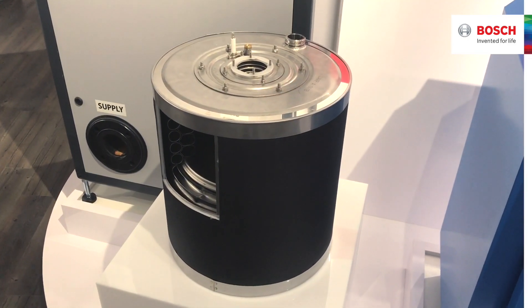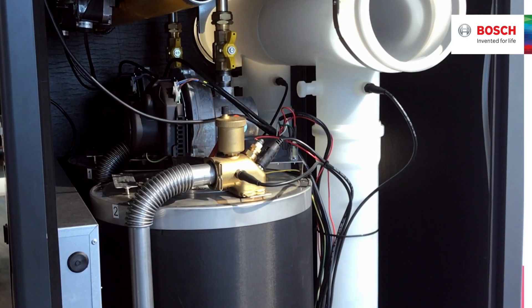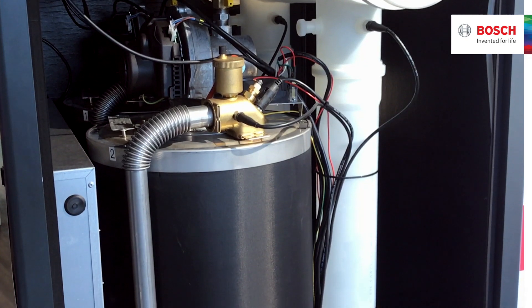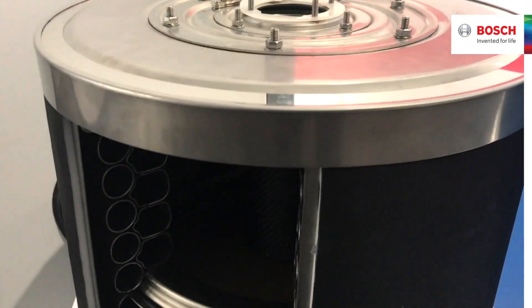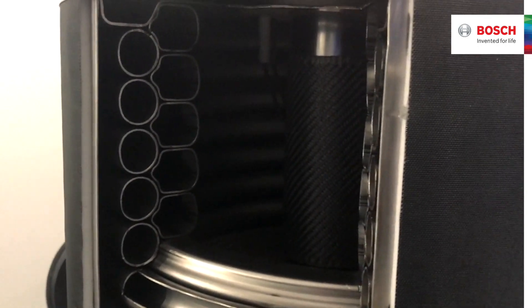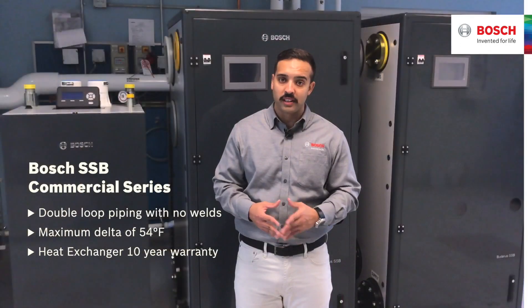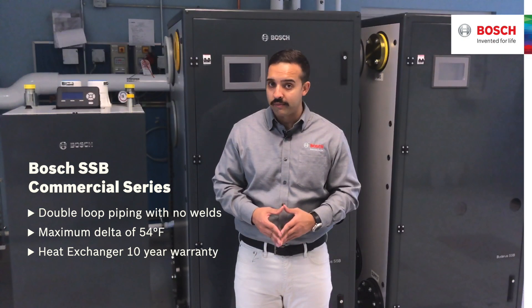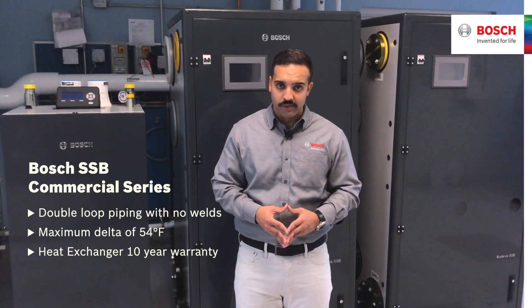The heat exchanger in all SSB boilers has a certified efficiency of 96% and a 5 to 1 turn down ratio. It is a water tube design made of 316L stainless steel with double loop piping circuits that has no welds on the tube. This allows it to expand and contract without creating stress on the unit, and allows for a maximum delta T of 54 degrees Fahrenheit.